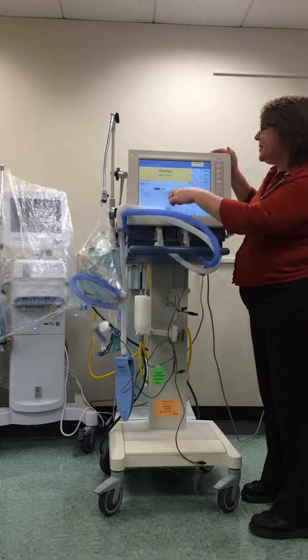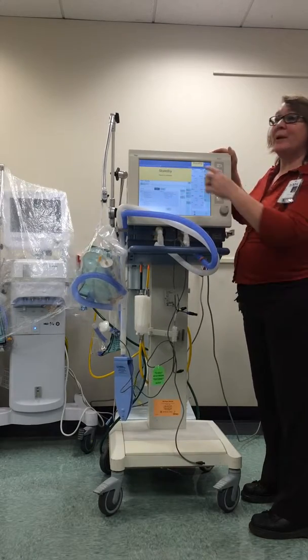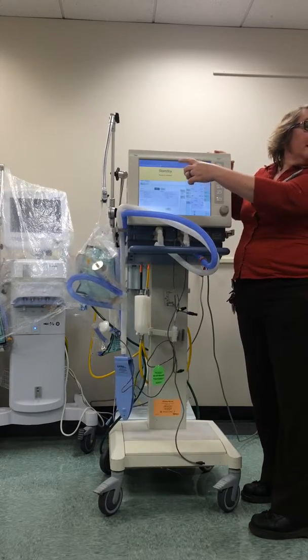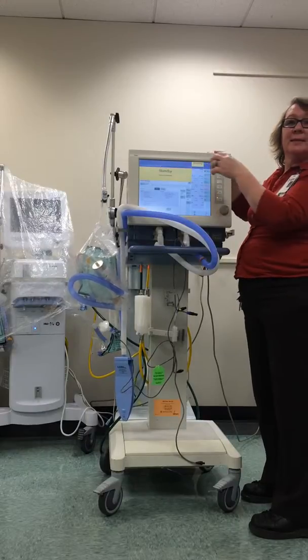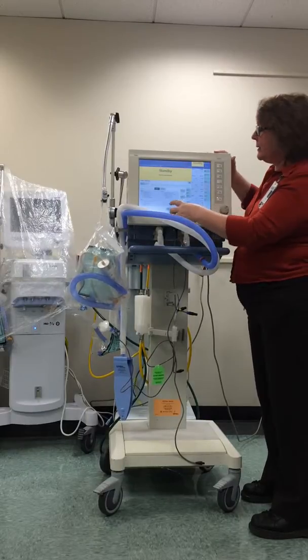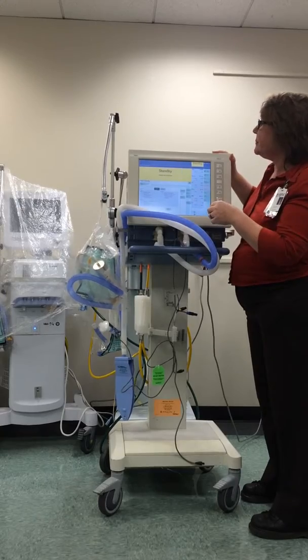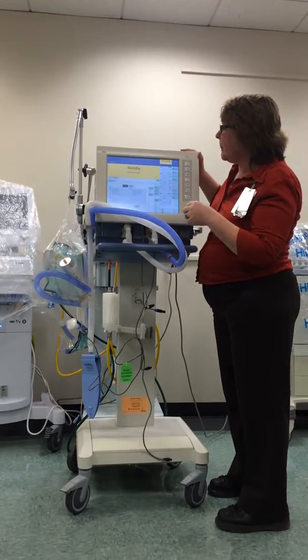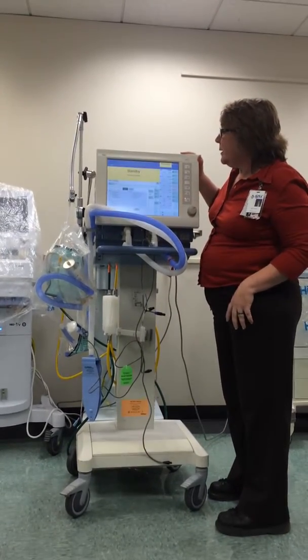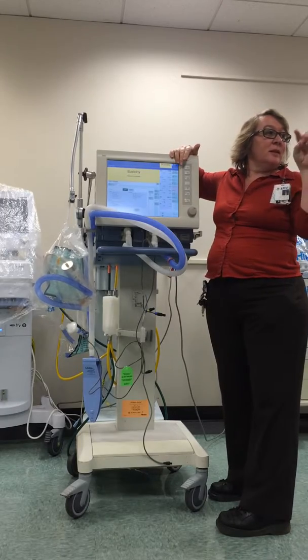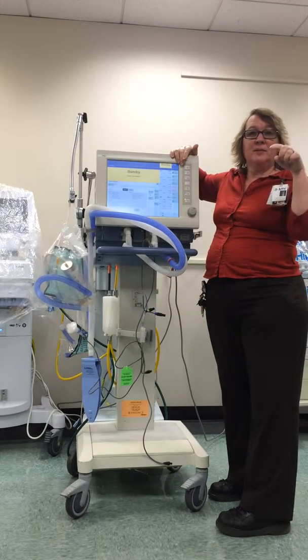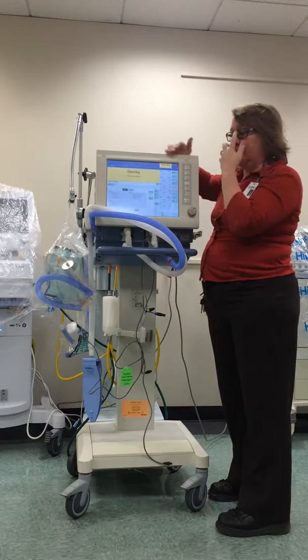And now it's going to go to the sensors, calibrate flow sensor. Now we have something else come up with the word Neo flow sensor in it. Do the same thing as the last time. Do next test. Because that will give you dashes in those areas. You don't want Fs. F means failed and it can't have anything failed.